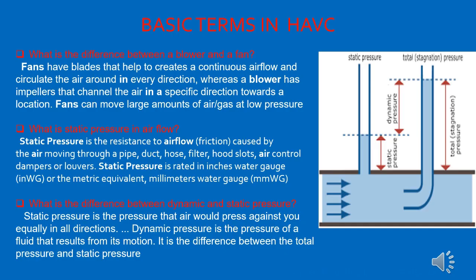There are a few common HVAC terms related to the AHU. What is the difference between a blower and a fan? A fan has blades that help increase continuous airflow and circulate air in every direction, whereas a blower has an impeller that channels the air in a specific direction towards a location. Static pressure is the resistance to airflow — the friction caused by air moving through the duct, pipe, hood, slots, air control dampers, louvers, etc. Static pressure is rated in inches water gauge.